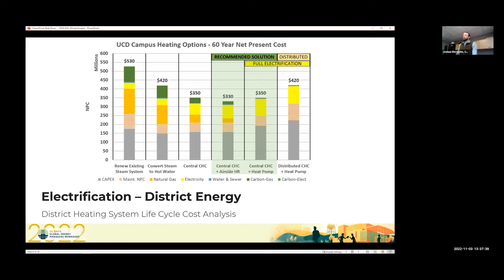we saw it was, in the long run, more feasible and cost-effective to install the hot water piping and have a centralized heat recovery chiller plant that ties into our centralized cooling system as well. There are some other options shown here, but what's important is that this hot water system with heat recovery was not only a big opportunity to save energy—with low temperature hot water compared to steam, less losses, and heat recovery potential—but it's also a pathway to full electrification. That's the path we're on.